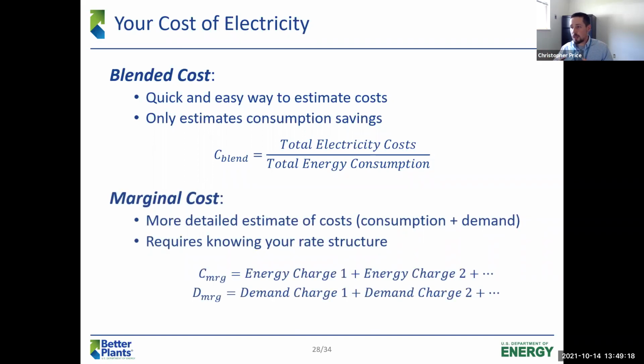A more detailed way of capturing your cost is the marginal cost, which requires that you really know your rate structure inside and out. Essentially, you would look at your rate structure and identify all the charges related to kilowatt hour consumption, and add those together. That is your dollar per kilowatt hour cost of energy. You would do the same thing for demand: everything that's billed on kilowatts, you add together, and say, for every kilowatt of demand I save, here's how much money I would save.